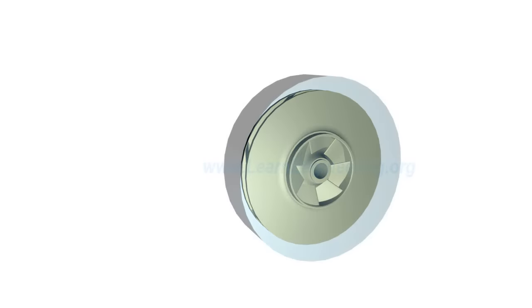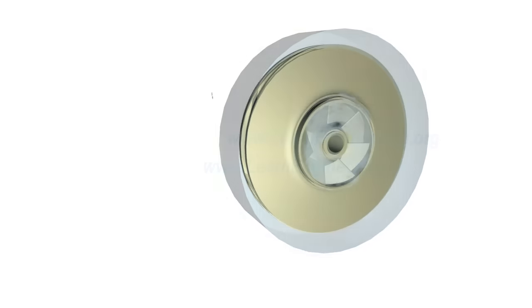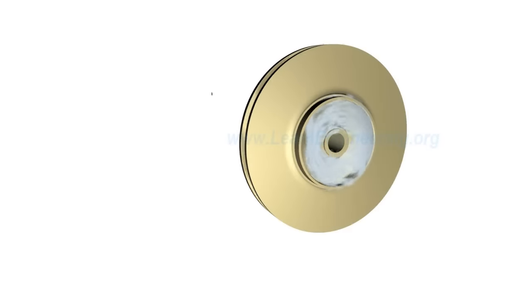The impeller is always immersed in water. When the impeller is made to rotate, it makes the fluid surrounding it also rotate. This imparts centrifugal force to water particles and the water moves radially out.